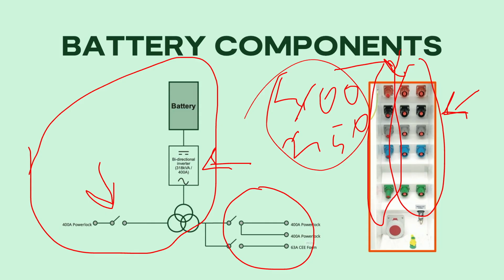What is the maximum amount of battery systems you can combine? Theoretically, there's no limit. Does it get unstable at some point? Probably, but we've done 10 in a cluster now with no problem—that's in grid forming. In grid following, we've done 20 at once without a problem; following should really be infinite, since you can just keep scaling it. Grid forming, as mentioned, we've done 10 very successfully, no problem, but that's where we're having to form the grid, so there are more intricacies involved.